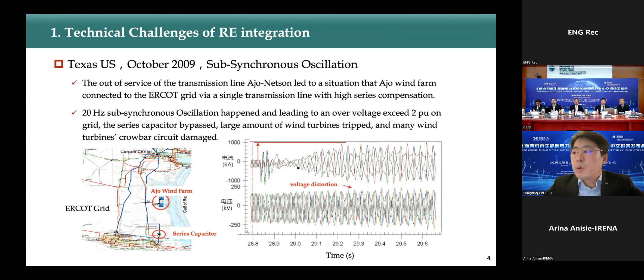In the case of a weak connection, a 20 Hertz subsynchronous oscillation happened, leading to a 2 per unit overvoltage on the grid, which caused a large amount of wind turbine tripping, and many wind turbine crowbar circuits were also damaged. We can see the grid structure and converter control play very important roles in this phenomenon, which is quite different from the conventional SSO or SSR that happens on synchronous machines.